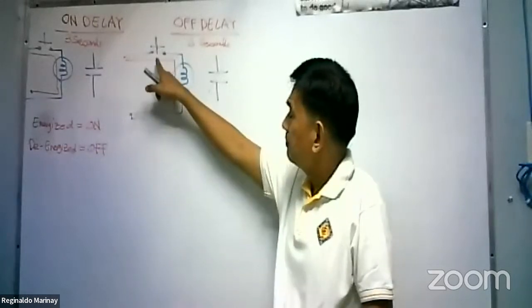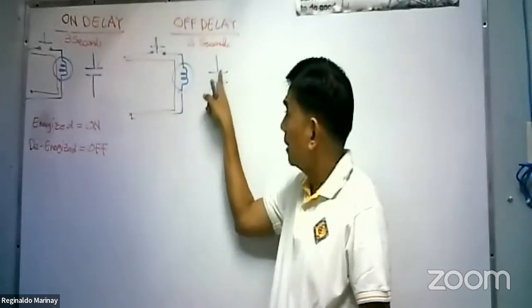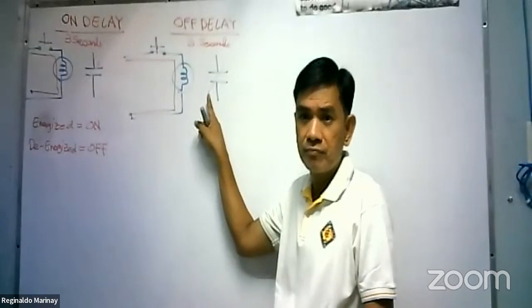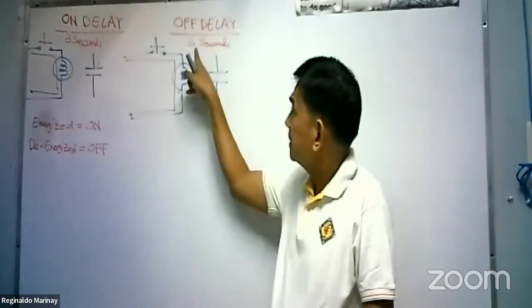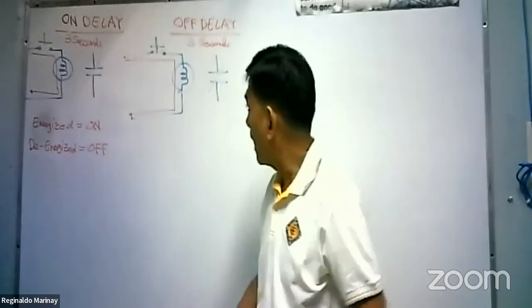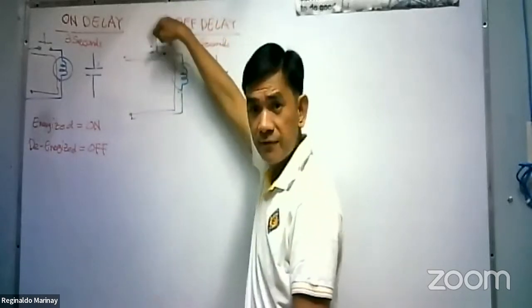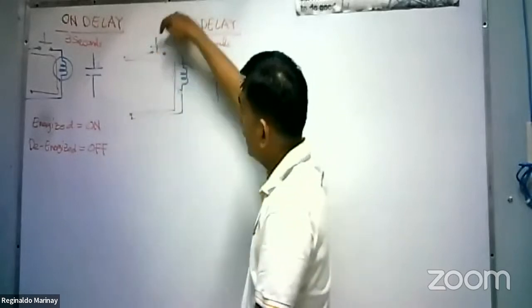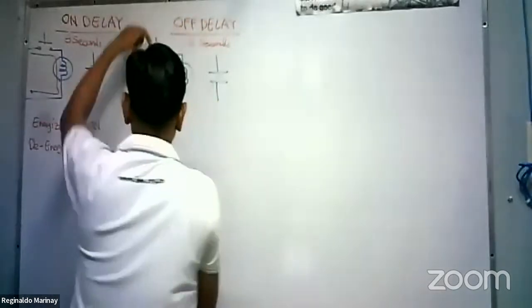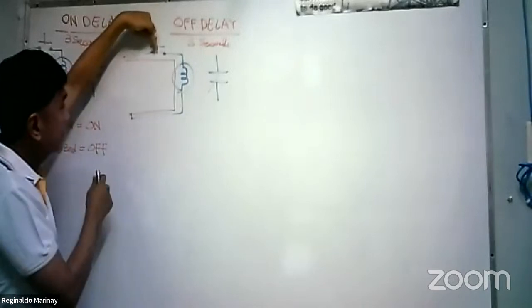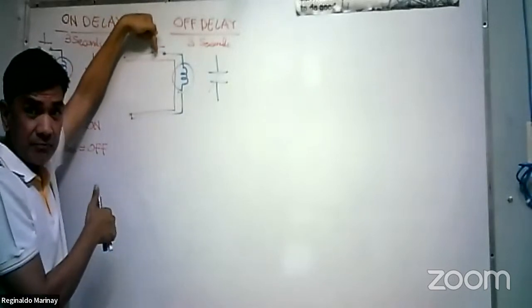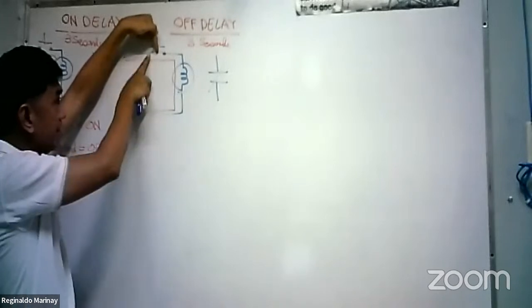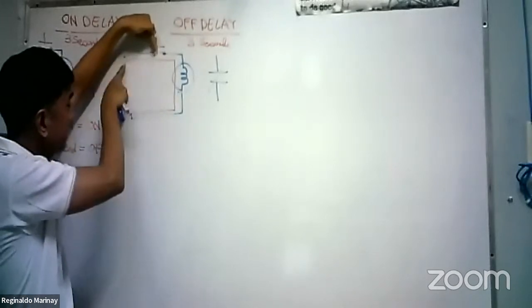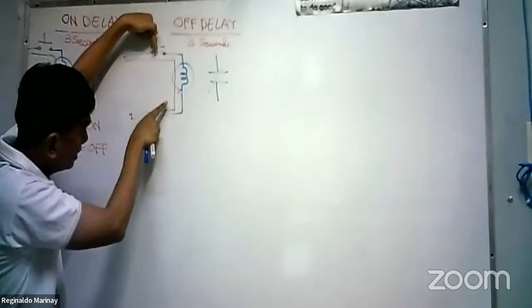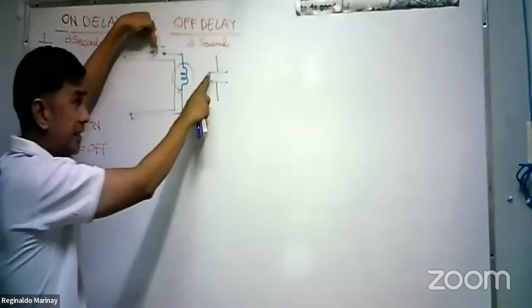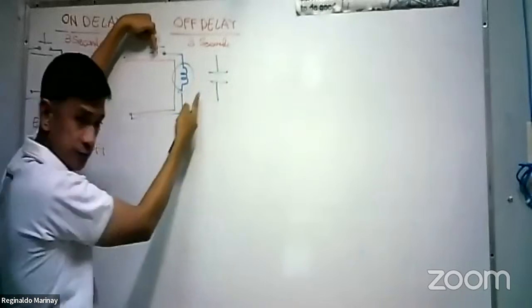Remember, what happened when this becomes energized, this becomes closed. I have a 3 second setting. Now, I will de-energize this. Of course, again. I will press this. My finger is still on the button. Pop. Okay. My finger stays there. Okay. Of course, that is closed. The contact is closed. Current will flow from line 1, energizing your holding coil, going to line 2. And this right away will become closed.